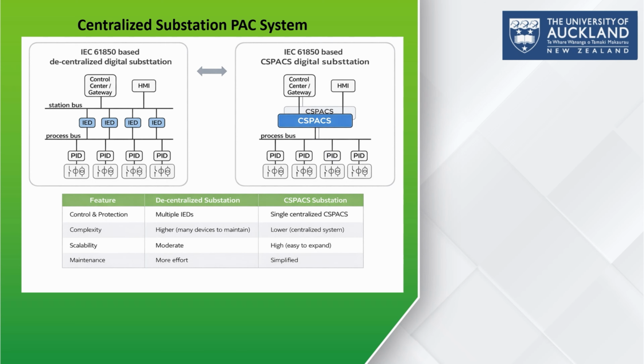The IEC 61850 based decentralized digital substation uses multiple intelligent electronic devices, that is IEDs, each performing specific protection, control, and monitoring tasks. At the top, a control center or gateway and HMI manage overall substation operations and provide the human-machine interface for operators, right? The IEDs connect to the substation bus and communicate with the control center.